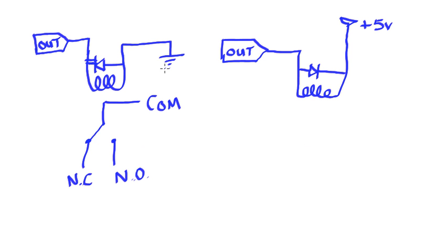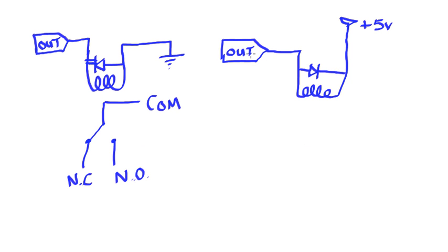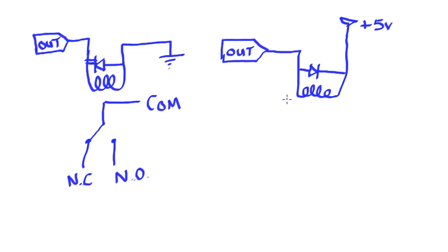One note back on this particular drawing. Remember that with sourcing, this device will come on whenever this goes high. It'll go off whenever it goes low. With the sinking method, this output will go on whenever the output goes low, and it will go off whenever it goes high. So there is a difference in how this operates, both from the logic level and from the electrical connection point of view.